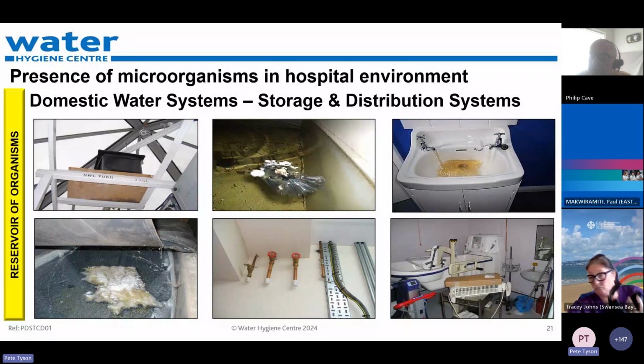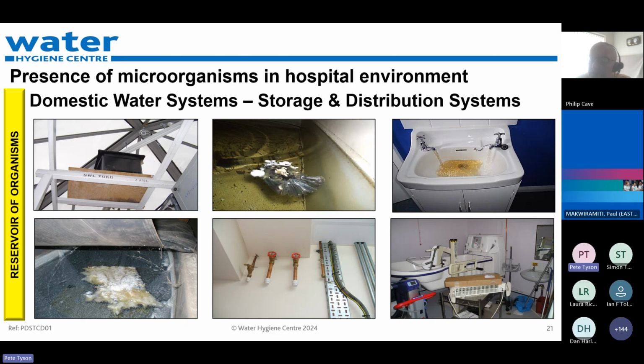So let's say we have some cold water storage tanks that are oversized, so there's a poor turnover, they are poorly configured and therefore gaining heat. We've got some hot water generators that may be undersized, so not achieving temperatures, not set at the right temperatures, or poorly configured. And our distribution system may have blind ends, dead legs, little used outlets, be poorly configured, or gain heat due to a lack of insulation, for example. The hot water may sit beneath the cold water pipes and supply lines, and there may be other things in there like dead birds, or some other form of contamination.